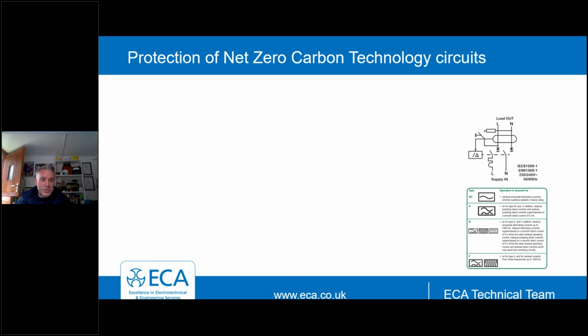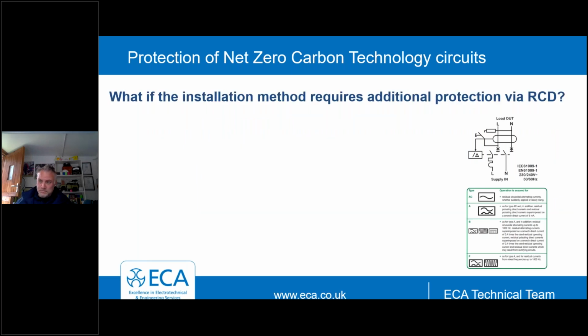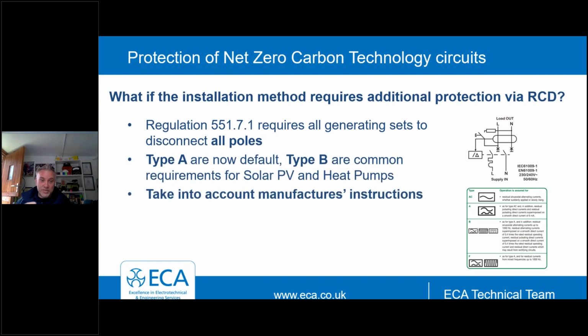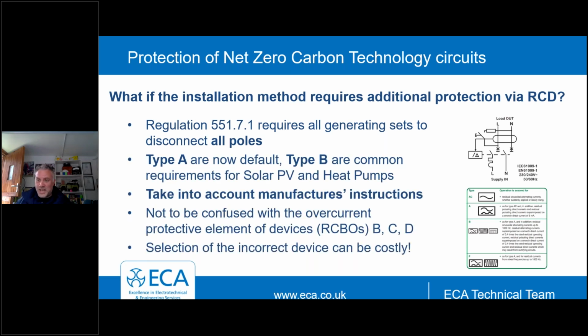When we're considering RCDs, we should make sure that we select the right one. Not only do we need to look at if it's unidirectional or bidirectional, we need to look at whether it is going to disconnect all poles. And that's been a basic requirement of regulation 551.7.1 anyway. So we need to make sure that all poles are disconnected. As we've mentioned, type A are now default and they're relatively low in price. However, some solar PV and heat pumps do require that, if you are going to use an RCD, it should be of type B, which is quite common. Again, there's quite a price increase on those, and we need to consider how we wire those in, and we'll come on to that shortly.